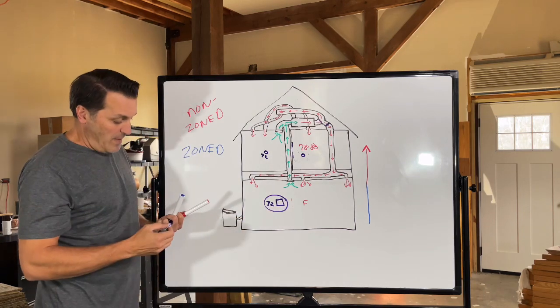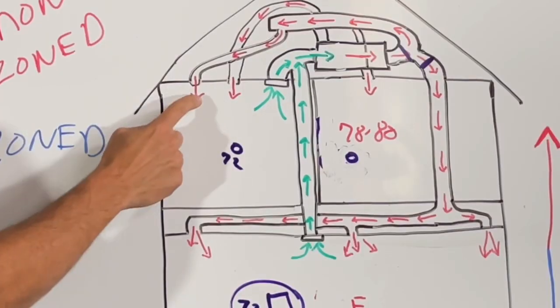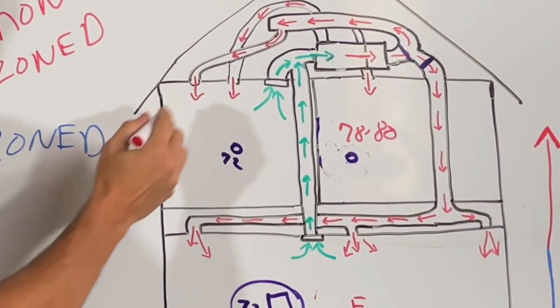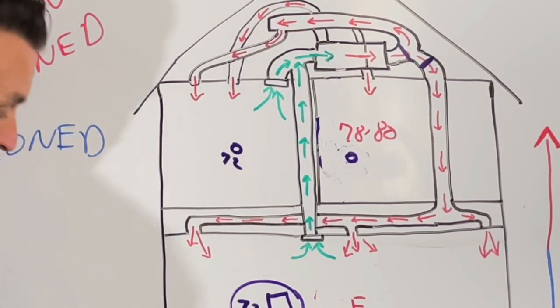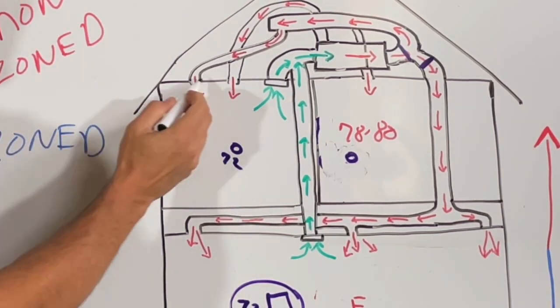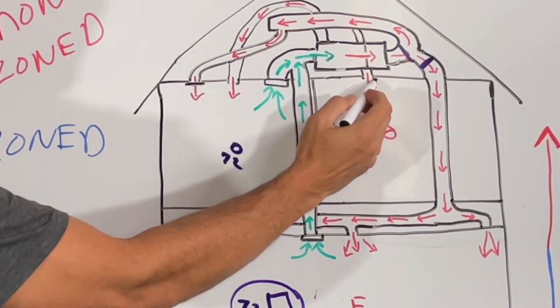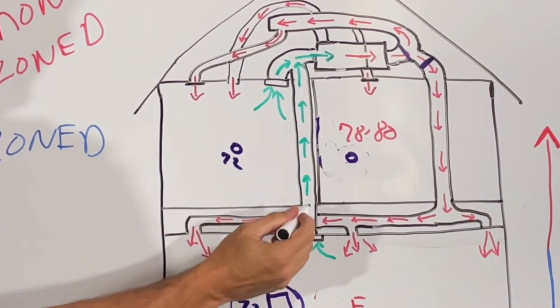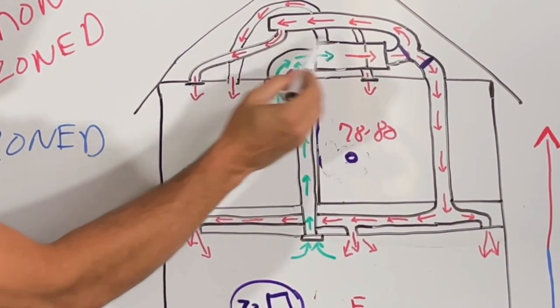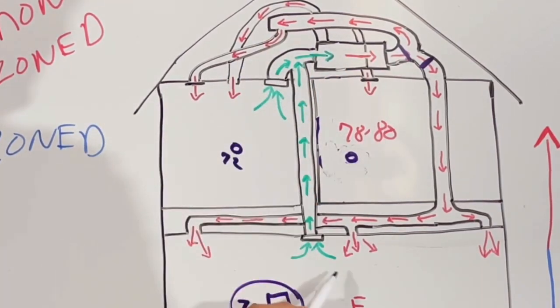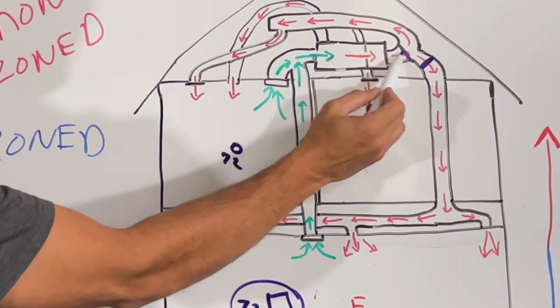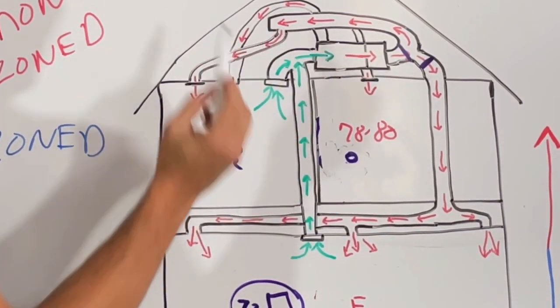It's not going to be possible, but the only thing that you can do is to shut some of the vents in the wintertime, the supply vents. You're going to shut some of those vents off in the wintertime and that's going to basically minimize that warm air flow. So you shut some of these vents off, maybe leave one vent on and let air come out. This warm air that you get down here from the vents, remember the red air would be the heat. The green is the intake. So one intake per floor, it goes into the unit, turns over to heat, and then it exhausts out through the supply vents.